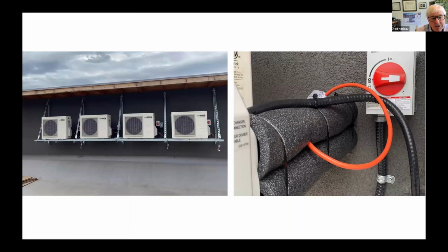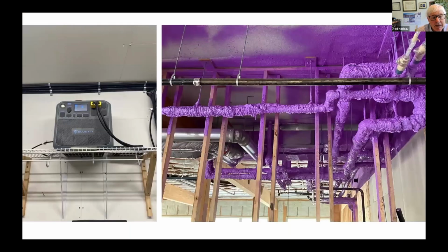There's just a quick picture of the Sandens. So those 4 Sandens are doing 30 units for hot water. The only issue we have with the Sandens is there is water out there. So we heat trace the water lines, insulate them, and then we have this little UPS backup system. But the most heat loss in these multi-unit buildings is actually in the recirculation system. So we spend a lot of effort making sure they're really well insulated, and that has saved us a ton of money in the multi-unit systems.